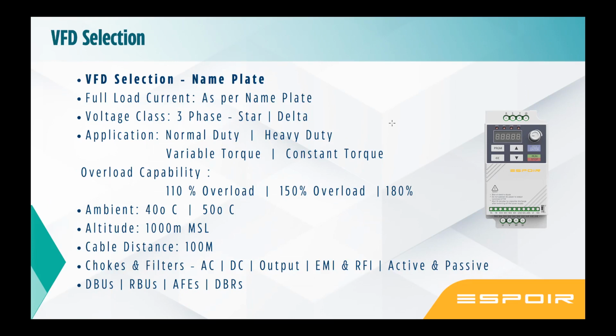Another aspect is cable distance. There are applications where the motor to VFD cable distance is higher. The physical distance could be near, but you need to actually calculate the cable distance, how the cable is running through different feeders. If the cable run is more than 100 meter, you need to really consider aspects like the corona effect, where the output voltage of the VFD is more than double at the terminal. It creates heat, it creates noise, it creates a lot of other factors which will eventually break the insulation of the motor, and probably the cable can get burnt and the motor winding can get burnt. So you need to be very, very careful on the distance between the motor and VFD.